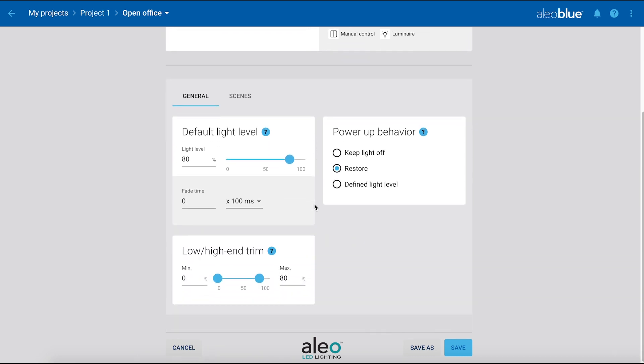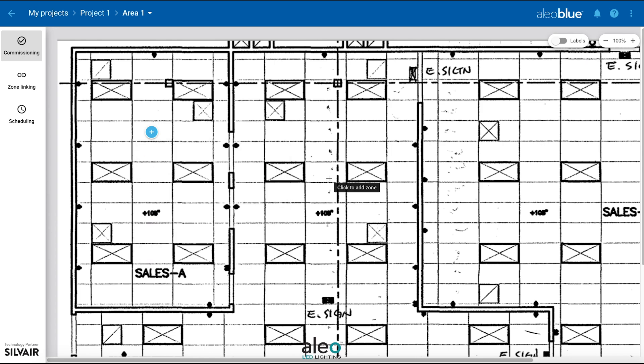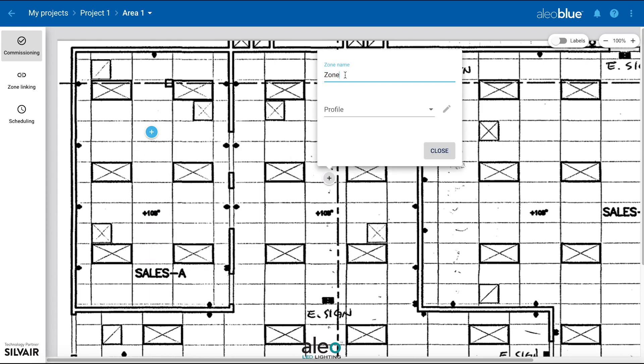We will also adjust the high-end trim of the zone, which can be done for other scenarios as well. We will be setting the high-end trim to 60%, meaning at full light output, the fixtures will only be able to reach 60% of their full output.